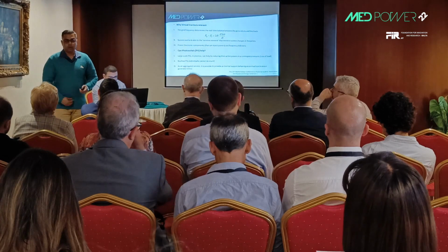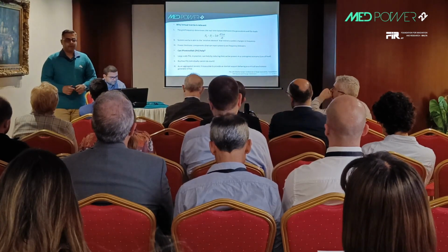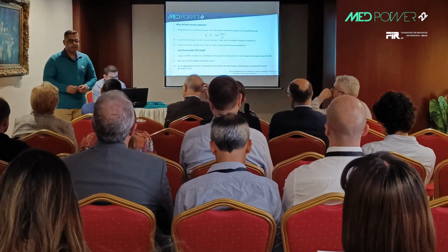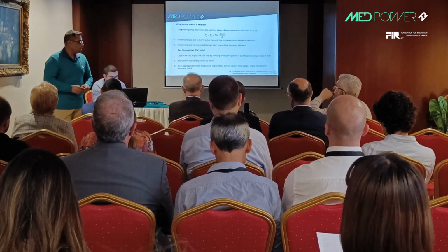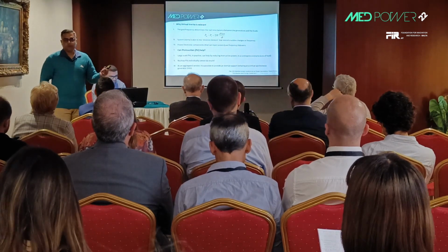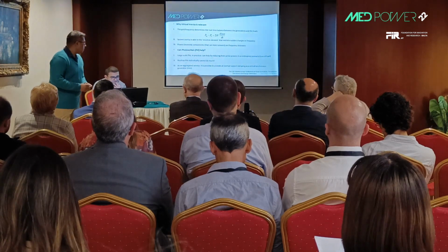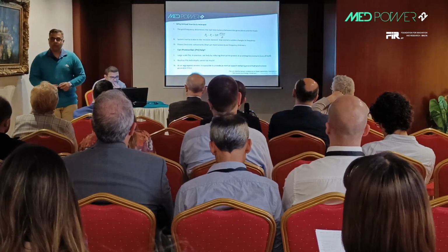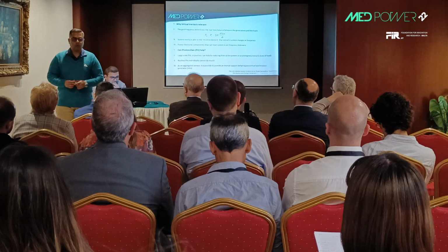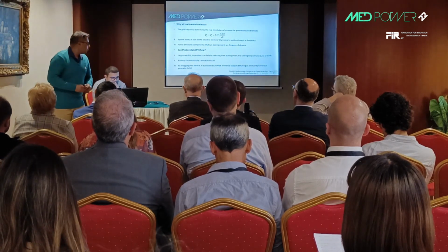Nowadays we have regulations from the electricity authority that in case of a frequency swell, the PVs should reduce their generation. The frequency swells happen when there is a loss of load in the system. But yes, rooftop PVs, the tiny ones, 3, 4, 5 kilowatts, of course cannot do much.